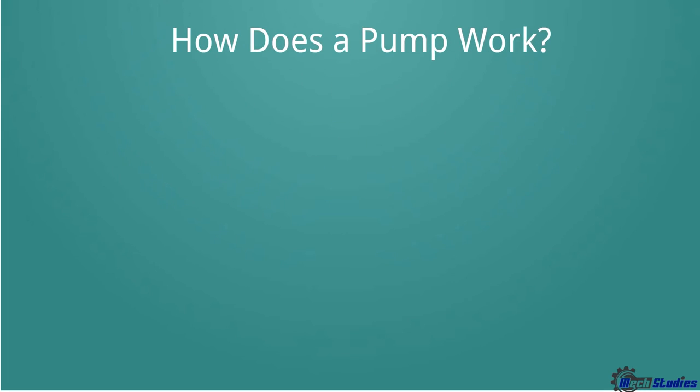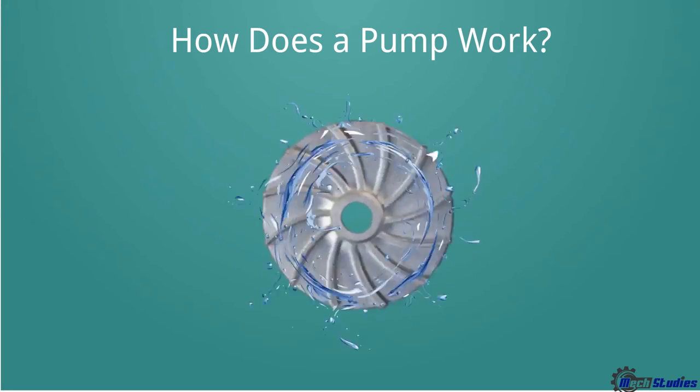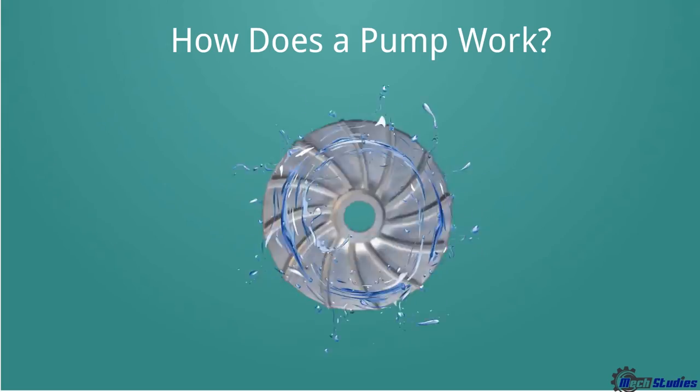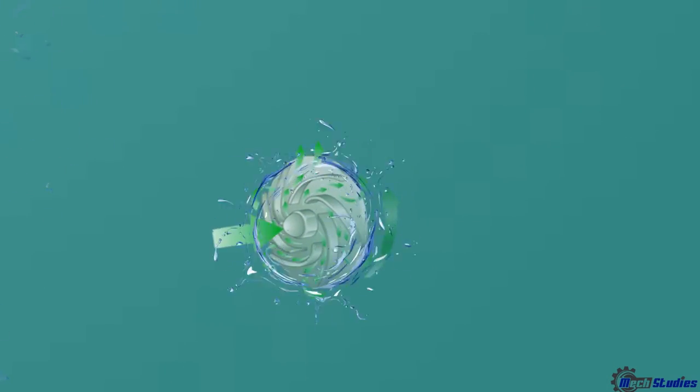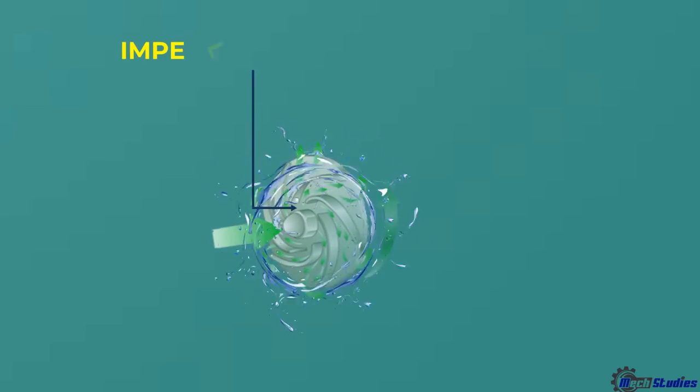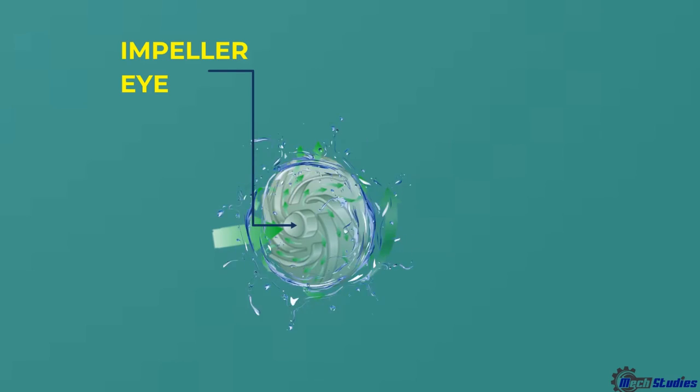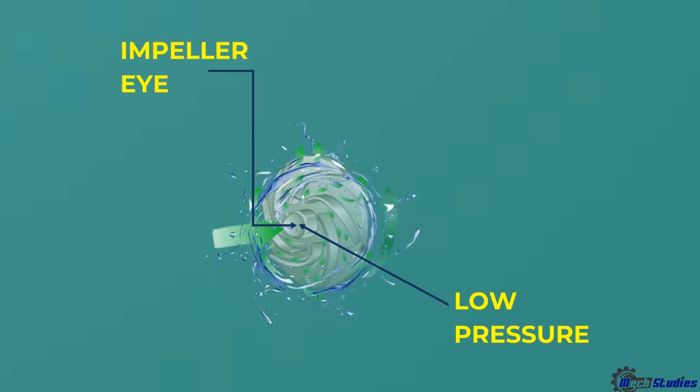Let's see how does a pump work, or how is the water introduced into the pump? Basically, we will learn the working principle of a pump. See, the impeller is rotating and associated water is also rotating with the impeller. This is the impeller eye, which means the center of the impeller. As the impeller rotates, due to its impeller design, low pressure will be created at the impeller eye.